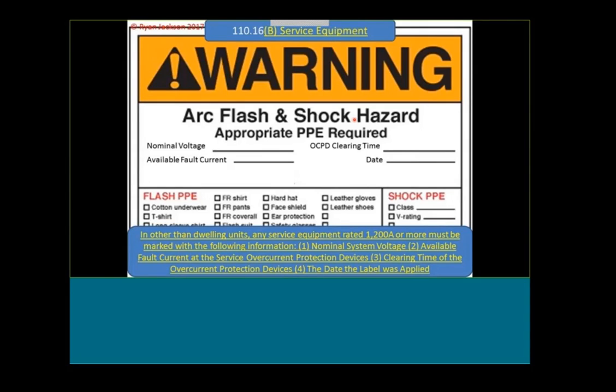Ever since 2002, there's been a requirement to mark certain equipment to warn qualified persons about the dangers of working energized on that equipment. We expanded the rules in 2017 to give electricians additional information so that if they have to work on it, they're better equipped to know what kind of personal protection equipment they might need and what the safe work practices are.